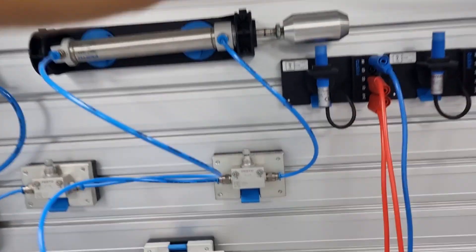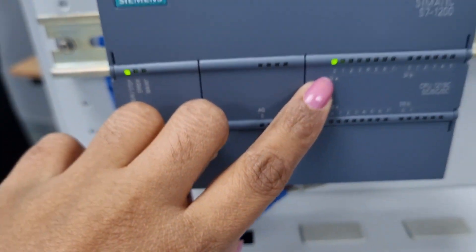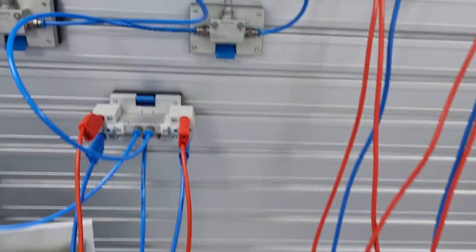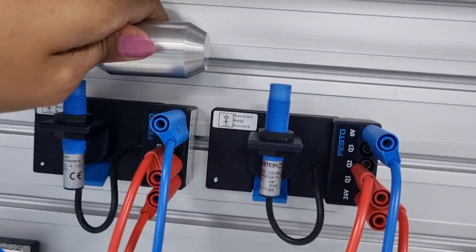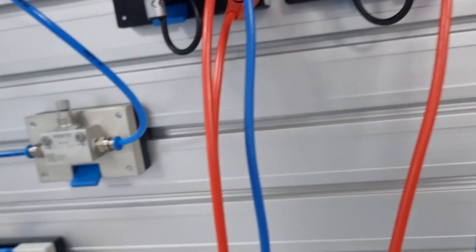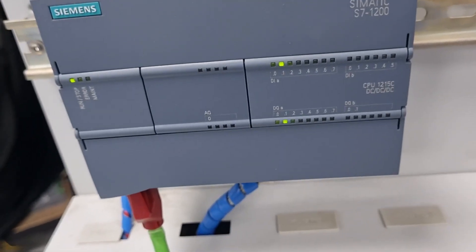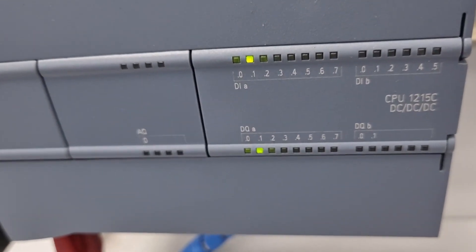Initially, this is in the retracted end position. Now you can see the sensor detects this particular position. You can see I0.0, this LED is on. That means the sensor output is high because it is detecting. If I change this position to the extended end position, this particular sensor will detect and give the output. You can see this is connected to I0.1. That sensor output is also high.